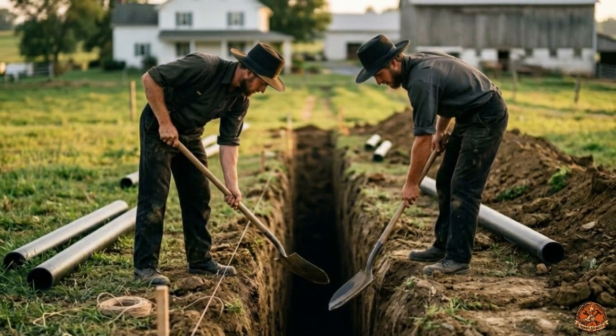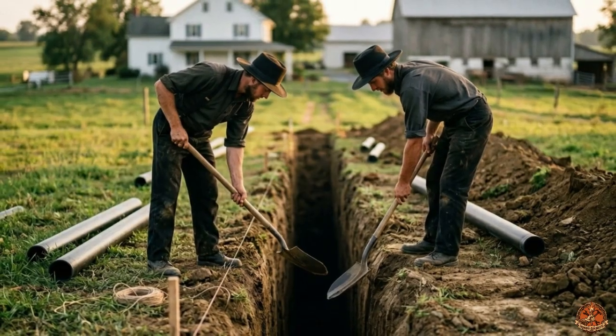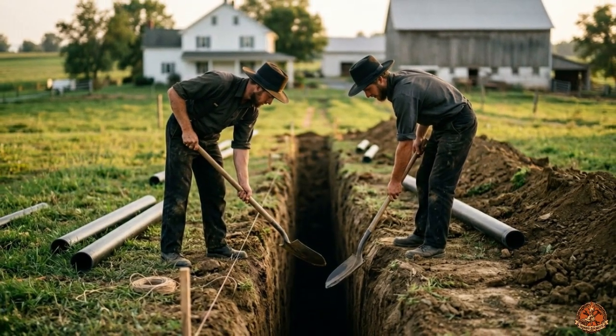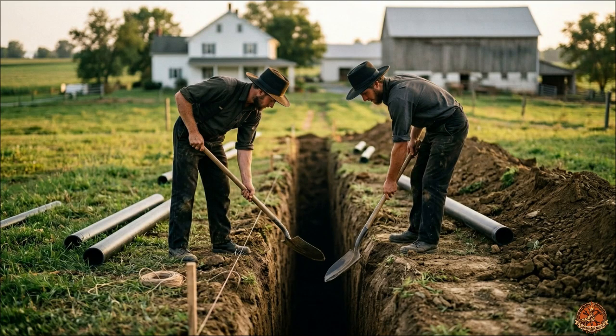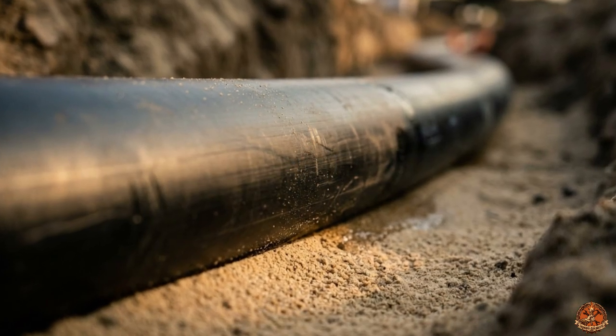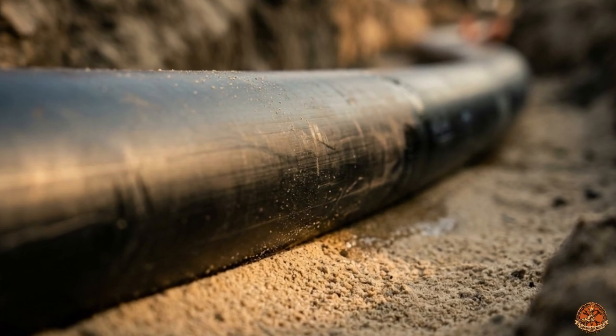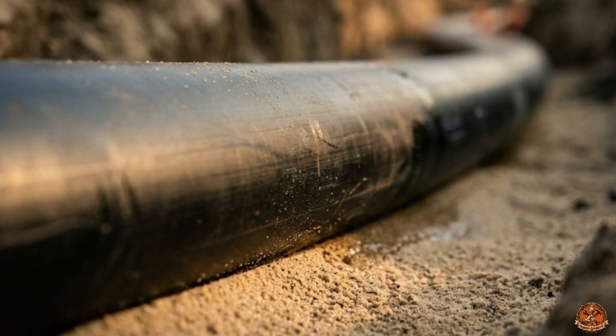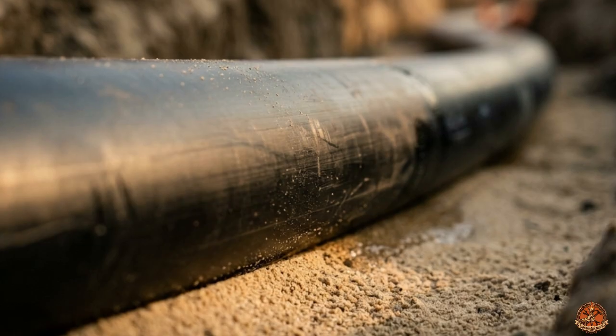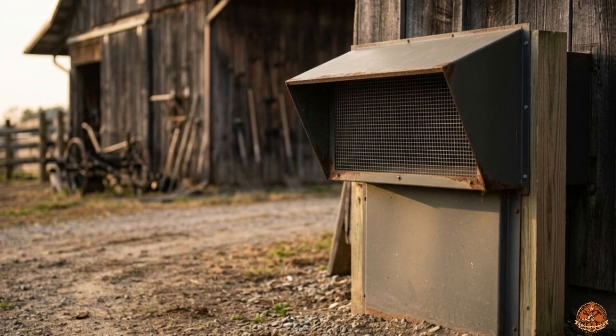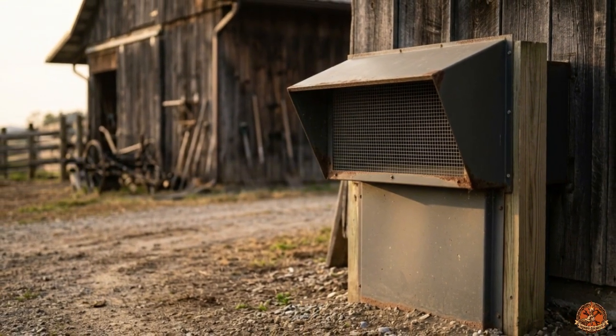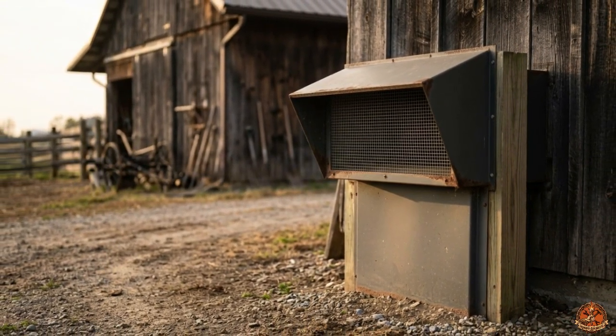For a pre-existing house, here's the setup. Excavate a trench 1.8 meters deep along any available land, your backyard, or the property boundary. Install smooth wall HDPE or PVC pipe 15 to 20 centimeters in diameter over a length of 30 to 60 meters. Using smooth wall pipe is mandatory. Corrugated pipe captures moisture and promotes mold growth. Place the pipe on a sand bed to ensure optimal thermal transfer. Give the pipe a 2% slope toward a drainage point so any interior condensation drains away without accumulating.